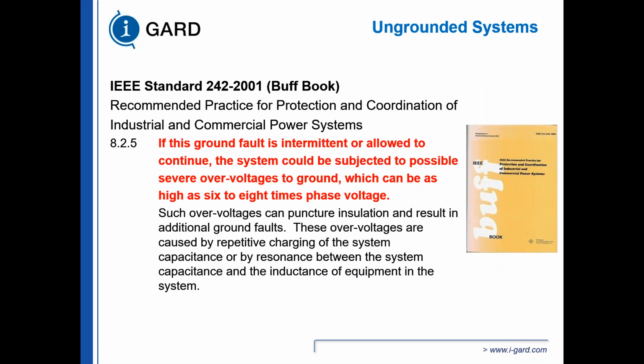If the first fault is intermittent or allowed to continue, 6 to 8 times overvoltages might occur on your system due to sputtering arcing faults. And this is significant because if you look at switchgear, the high pot level that we put on switchgear is about 2.2 kV. Anything above 2.2 kV with respect to ground, something is going to fail. So on a 480 or 600 volt system, 6 to 8 times the voltage, you're going to be above 2.2 kV. So something is going to fail someplace. And it's probably going to be in a location not associated with the ground fault. We've troubleshot many situations like this, and what people tend to forget is that ground is this magic conductor that connects your entire electrical system together.